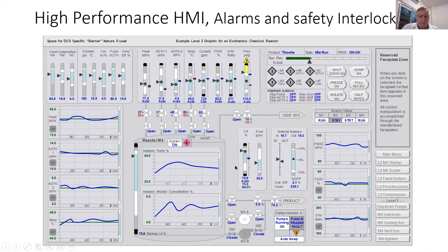So this trend here is all the time in the blue area, so that it moves to the left, and then you see here always the latest value, and this is from the history from the last 1 hour, 2 hours, whatever you set here. But you can see everything is okay. And that is what we mean with high performance HMI. And it shows also, especially the radar plot and some other symbols, that you can get much better and much more safe information out from this display.